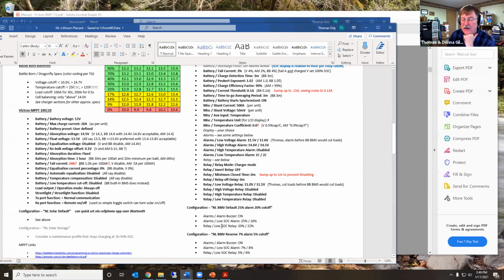And then I think the low state of charge also gets described as the discharge floor on another of the screens. So they had me set that at 0. So that meant it's going to rely on the BMV, the battery management system, the BMS, to shut that off. Correct, and that's a very common recommendation - let your battery deal with it. But I'm doing this defensively, I want 20% left in the gas tank. Yeah, so that's why I'm setting it like that.